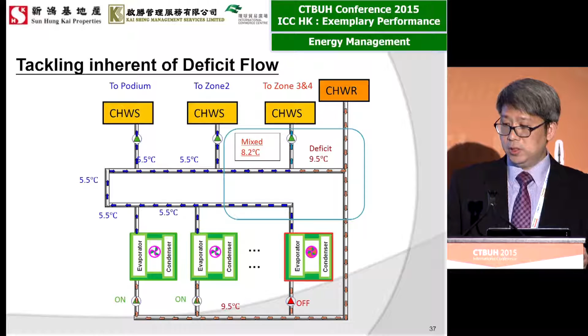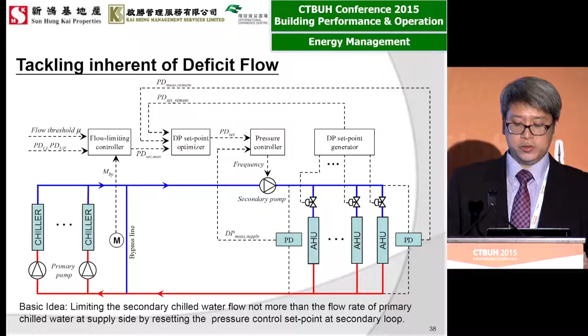Tackling inherent deficit flow. The inherent deficit flow appeared at the chilled water bypass pipe that caused high chilled water supply temperature, reduced the operational performance, and lowered the energy efficiency of the system. This has been tackled by adopting a flow limiting control strategy. By means of this control strategy, the flow rate of the secondary chilled water is always limited below the flow rate of the primary chilled water. Both operation performance and energy efficiency have been improved.